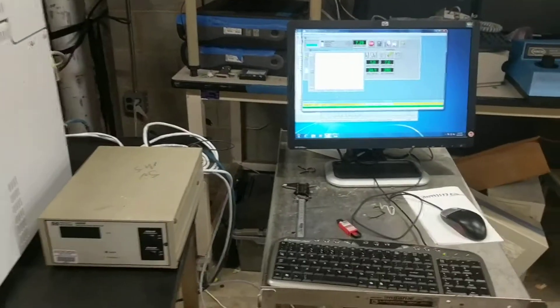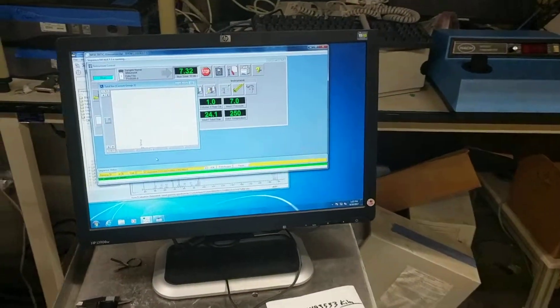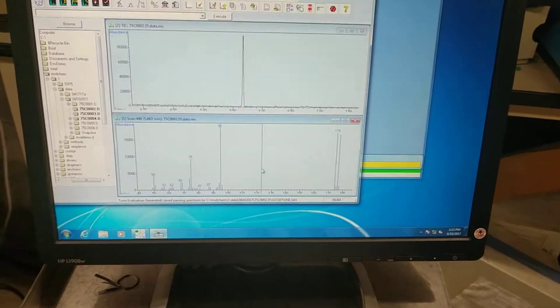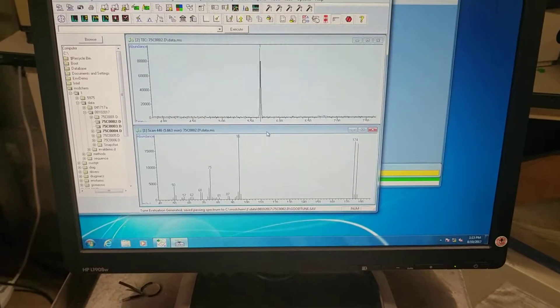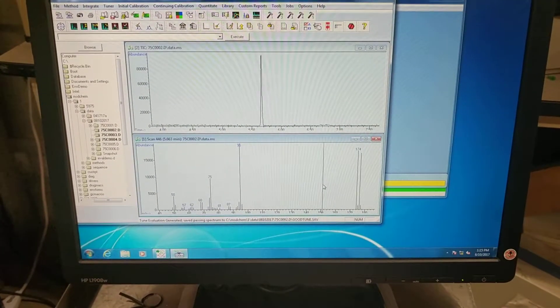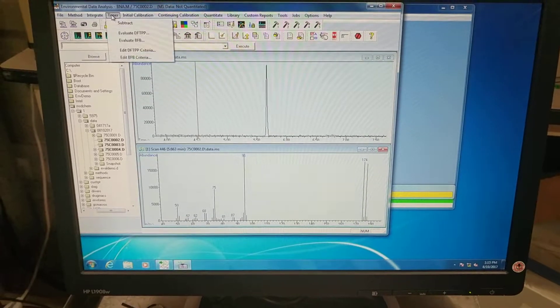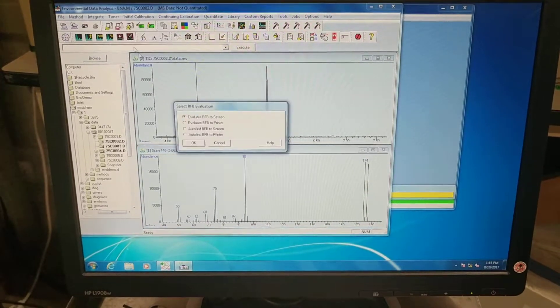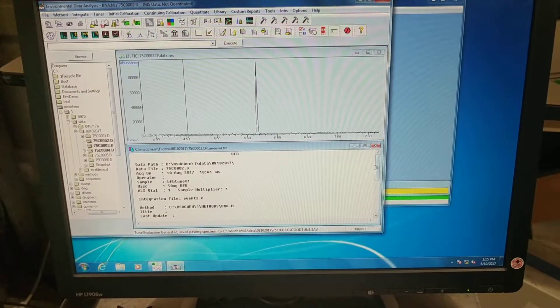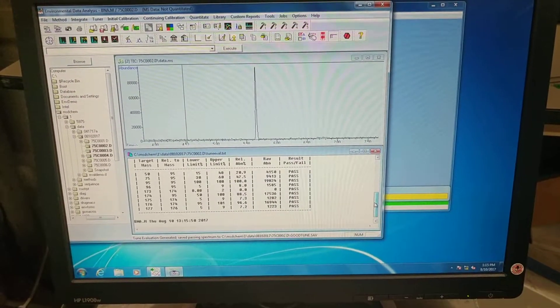We are running on Windows 7. We ran a sample before. Just to show you, this is a BFB EPA-type tune. You can see the spectrum from it. We'll go to Tuner, Evaluate BFB — Evaluate BFB to the screen. And we'll look at this and we pass.